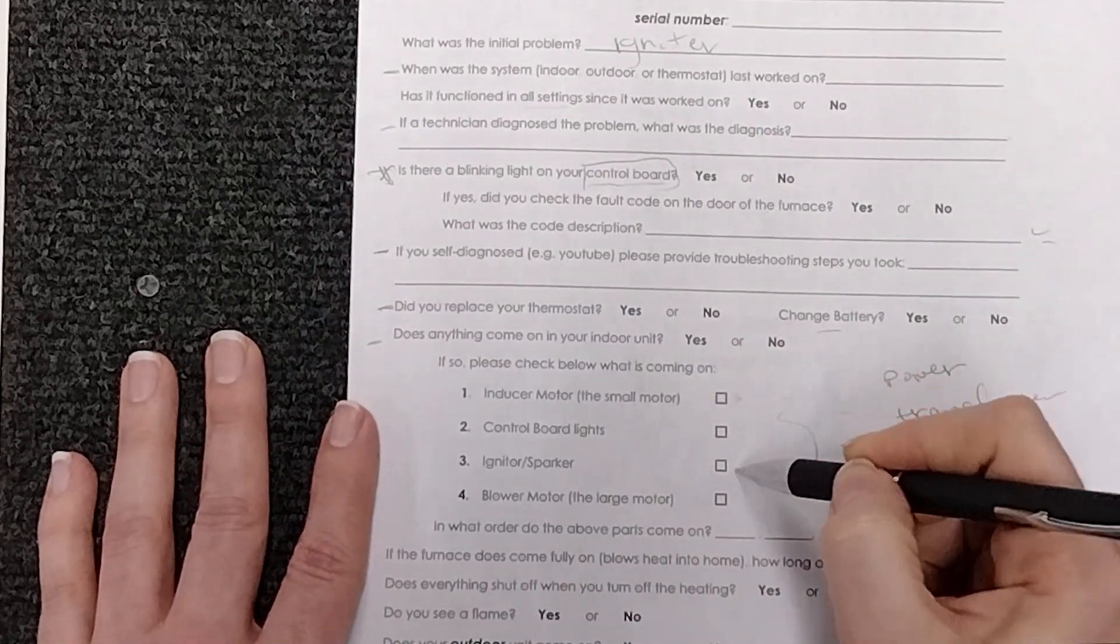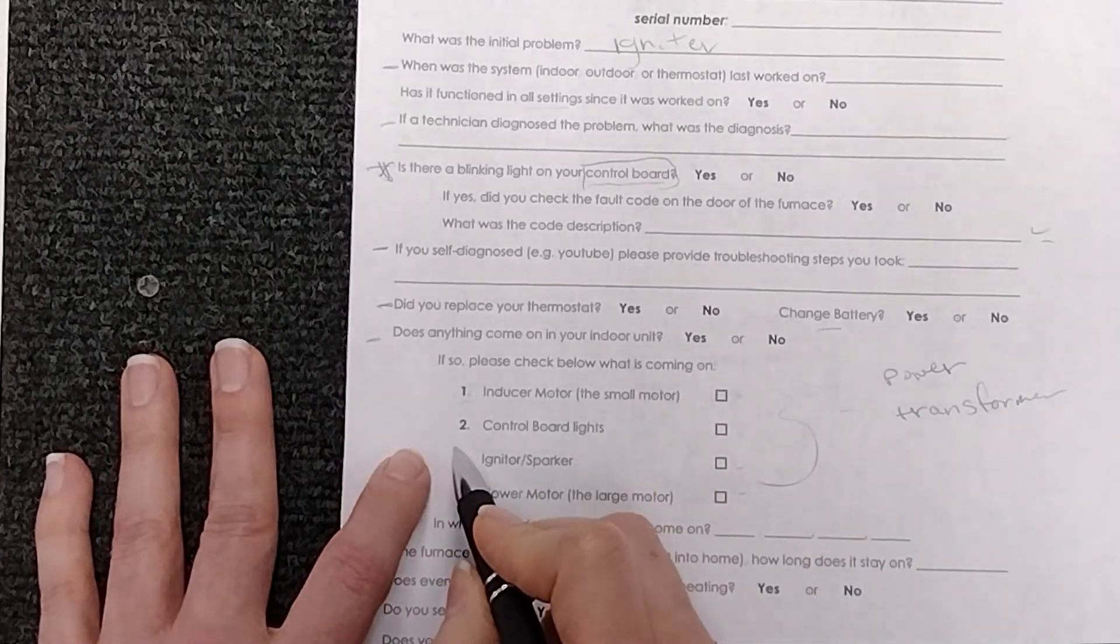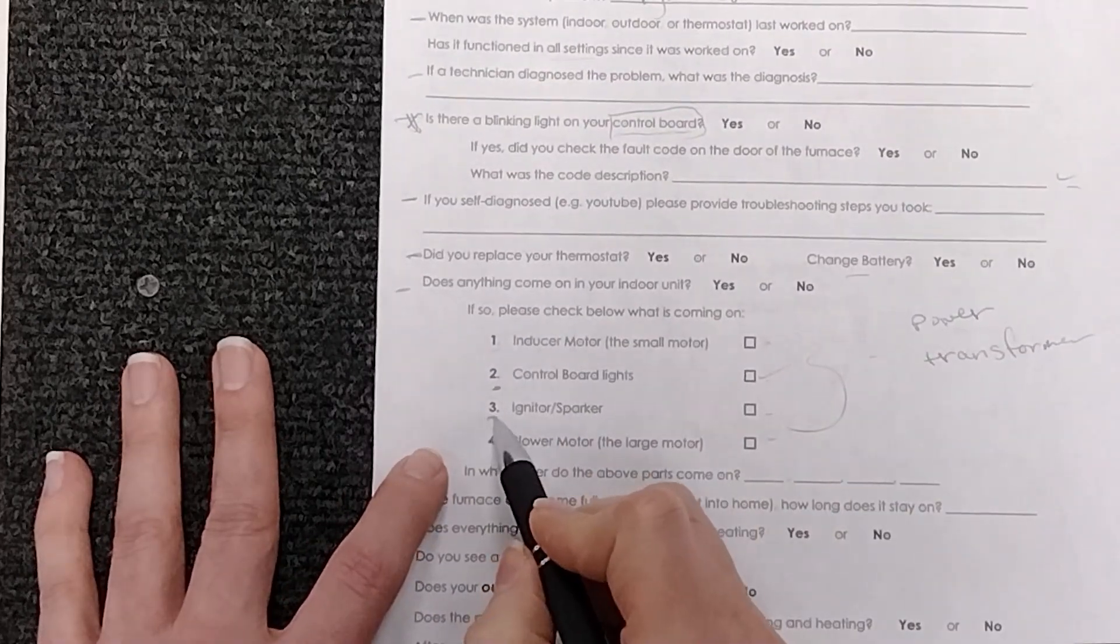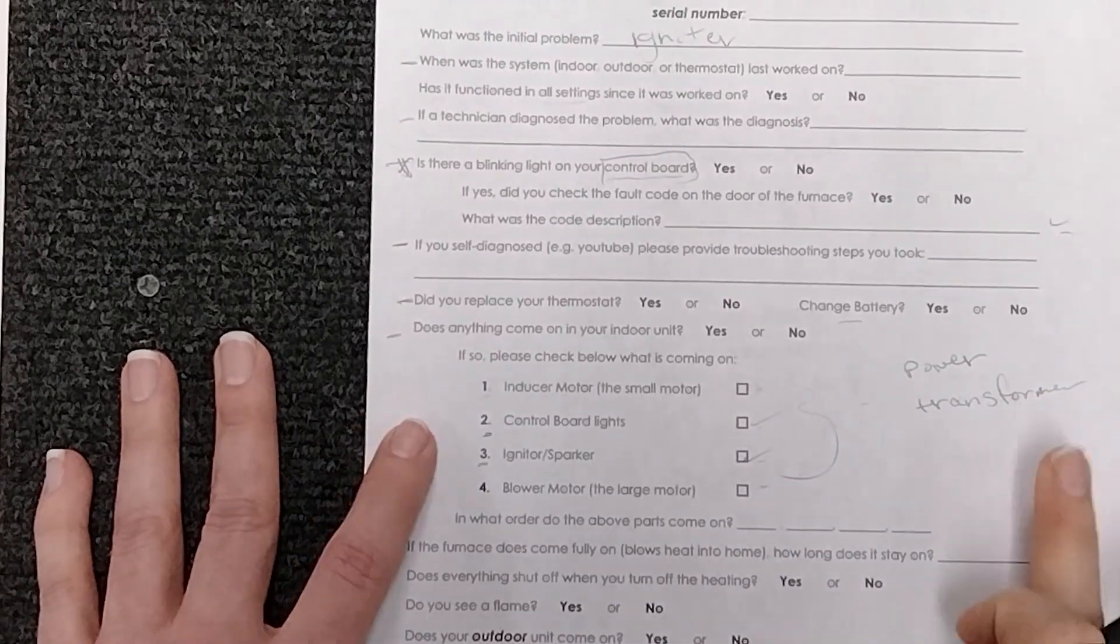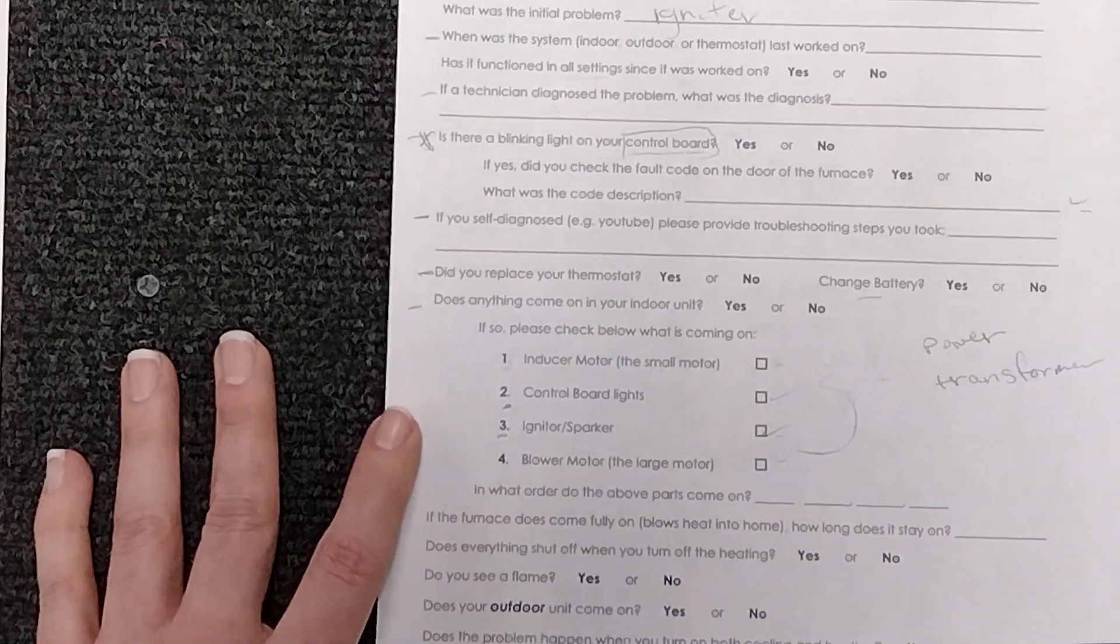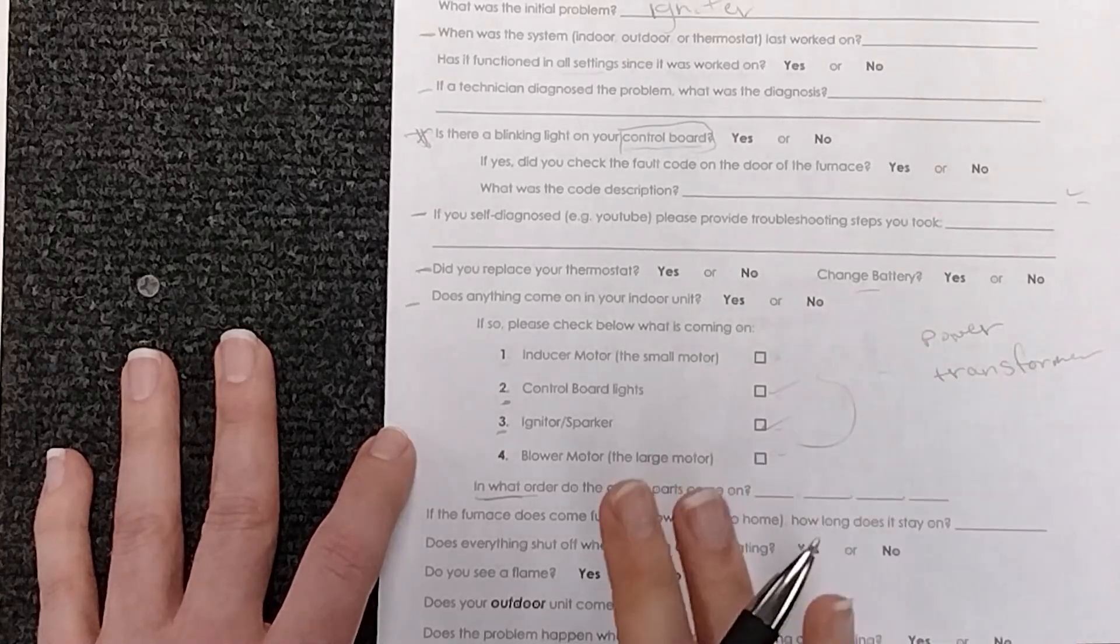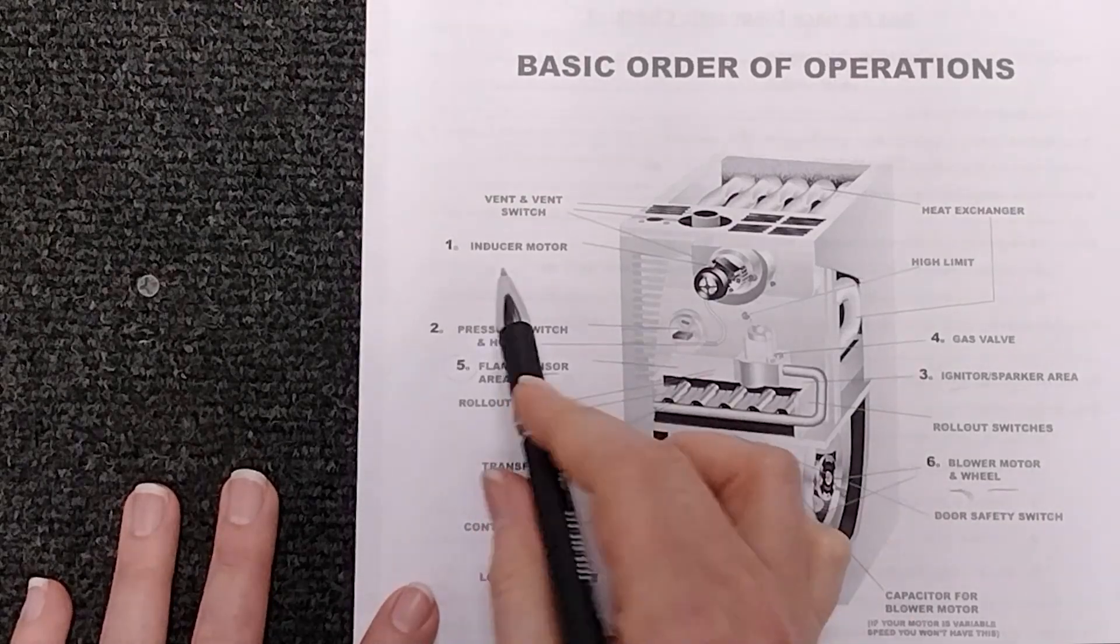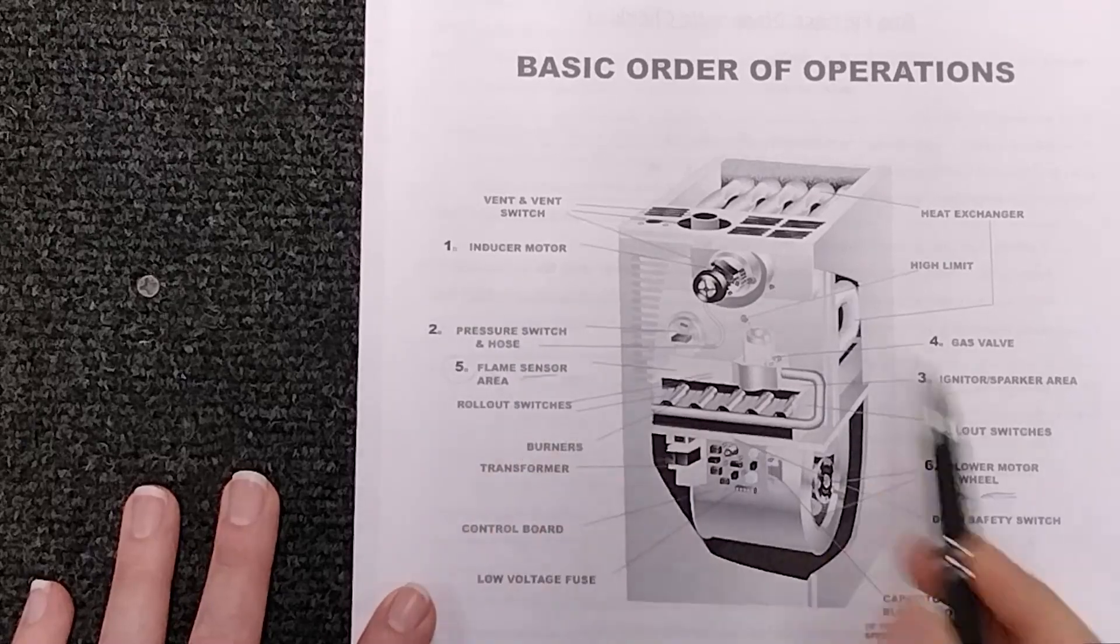So here's our checklist for what should be coming on. Inducer motor comes on first. Check. Okay. Control board lights come on. Check. The igniter or sparker comes on. Check. So on and so forth. List it out for yourself to figure out again where that problem is stemming from. And right here we've said in what order do these parts come on. So again if your inducer motor and your blower motor come on at the same time is that within our order of operations? No. No it is not. So clearly it's got something going on here.